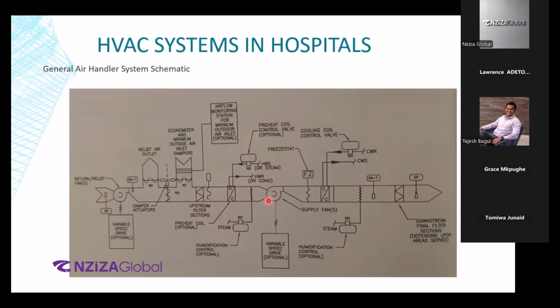Okay. Now over here, as you see, there is something called a variable speed drive. If it is DC motor, it will be variable speed drive. If it is AC motor, it will be variable frequency drive, right? Now this one is optional if you find it over here, okay? If you have those VFDs, VSD on the motor, variable air volume. If you don't have them, constant air volume. Make sense? Yes. Okay.